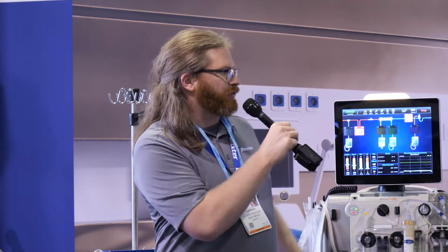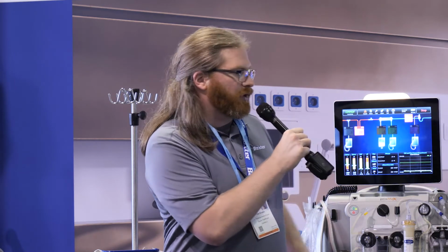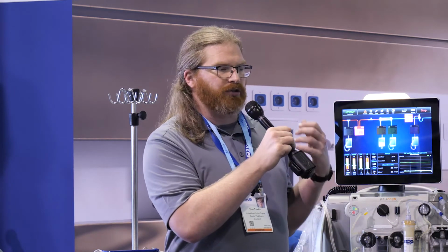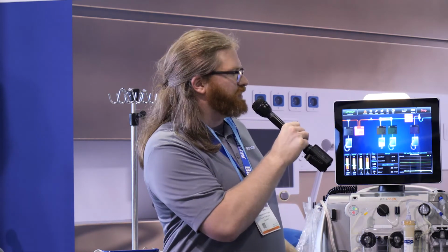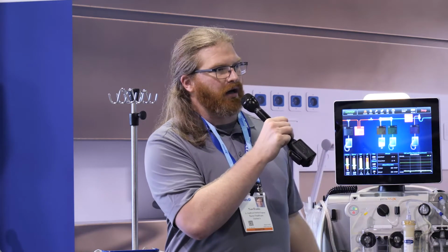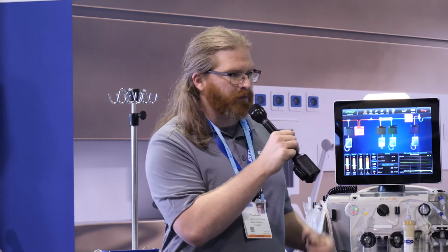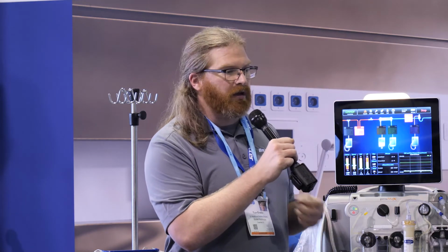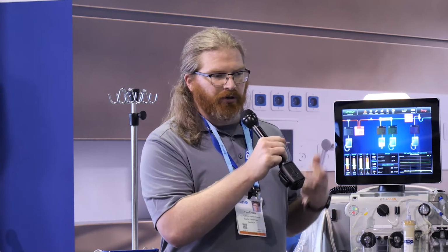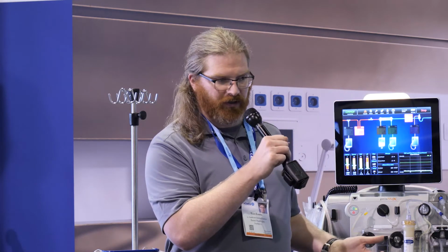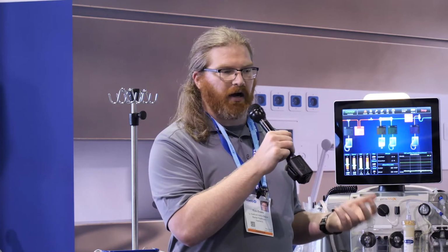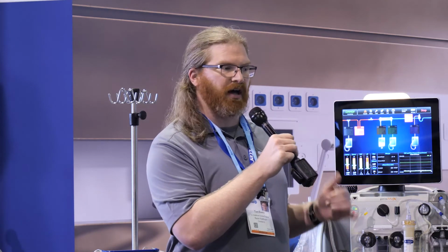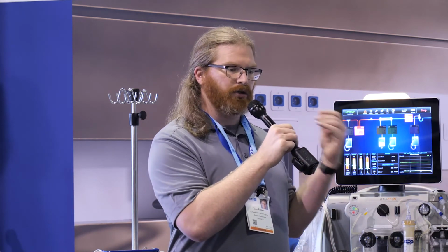So continuous renal replacement therapy on the Baxter Prismax starts up, and after the treatment has begun, the TrueView Connect on this Prismax device sends information directly to Epic over the hospital's wireless network using HL7 2.5 and is going to capture over 100 data points every minute for the duration of the treatment.